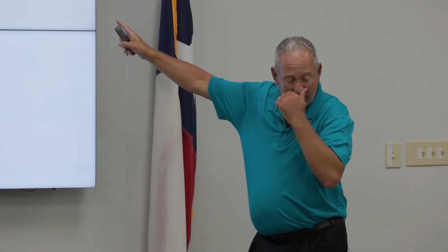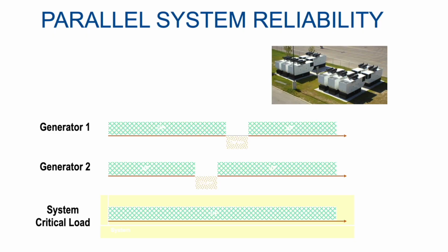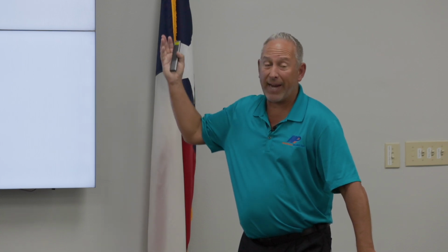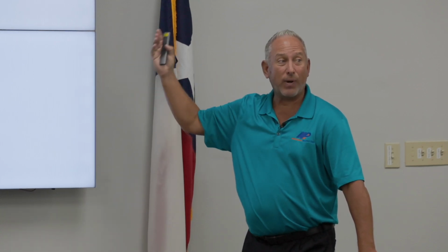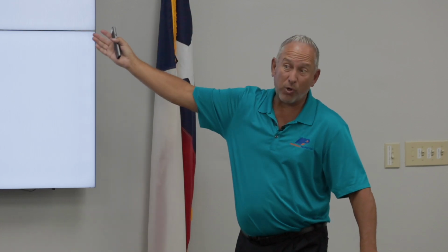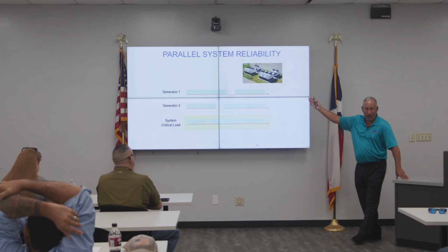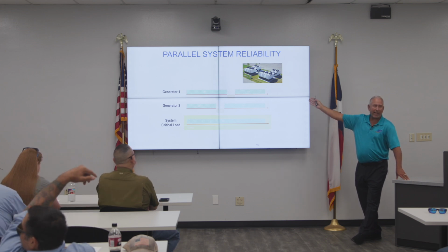So that world's changing quite a bit. This was an example, actually a big data center, this one happens to be in Canada. When it started, there was 1 generator on each pad. As that customer grew and brought in more loads, they just dropped another generator. Of course, you had to have the system designed to handle that ampacity of growth, you can't do it after the fact, you've got to have enough wire and distribution to handle the additional growth you're going to bring on. But the benefit is that right out of the gate, they didn't overspend or buy a huge generator that would be lightly loaded for a long time.